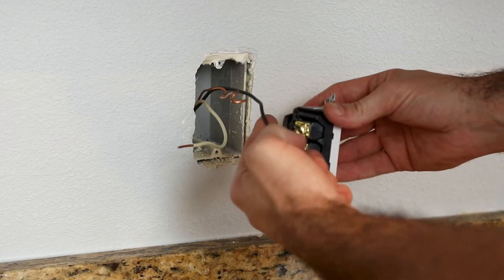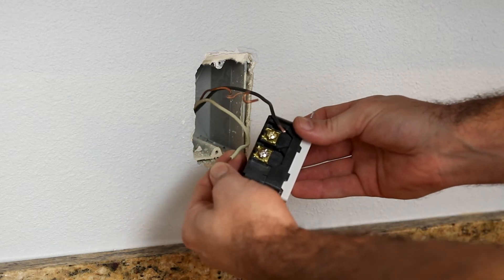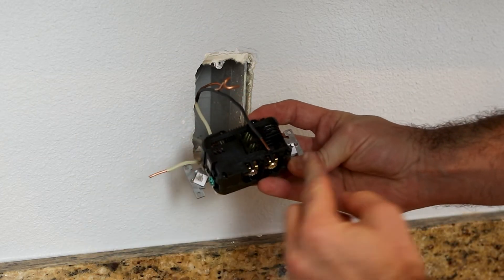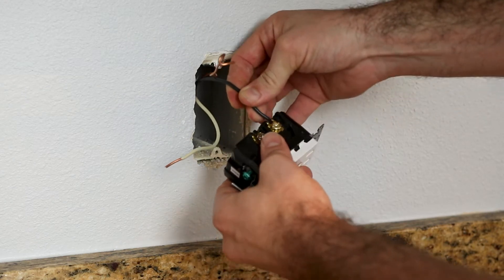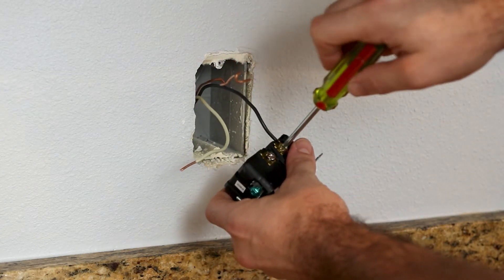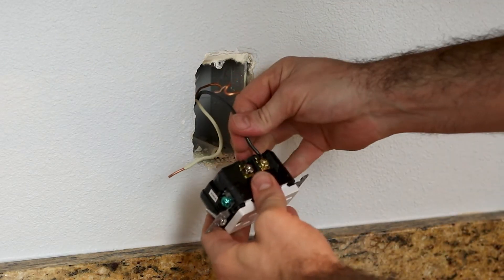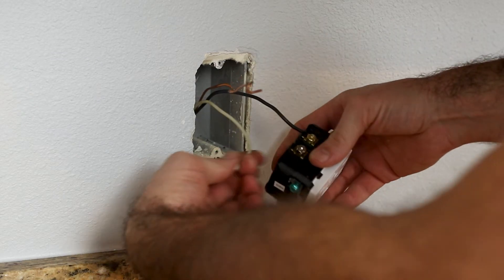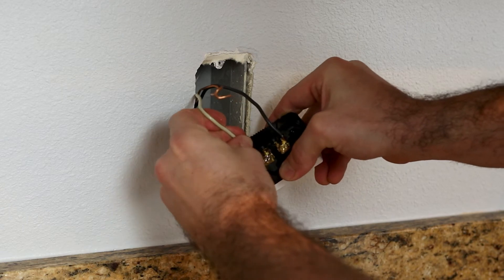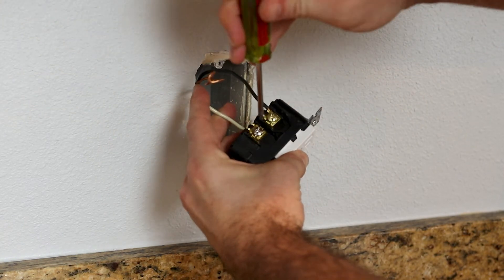So we have our gold screw, which is for our black wire or hot wire. We have our silver screw, which is for our white wire, which is our neutral. We'll go ahead and put that behind the tab right here and tighten this down. Make sure we have a firm connection that's not coming out of there. Now we're going to repeat the same for the black wire — put it behind the tab and tighten that screw up.